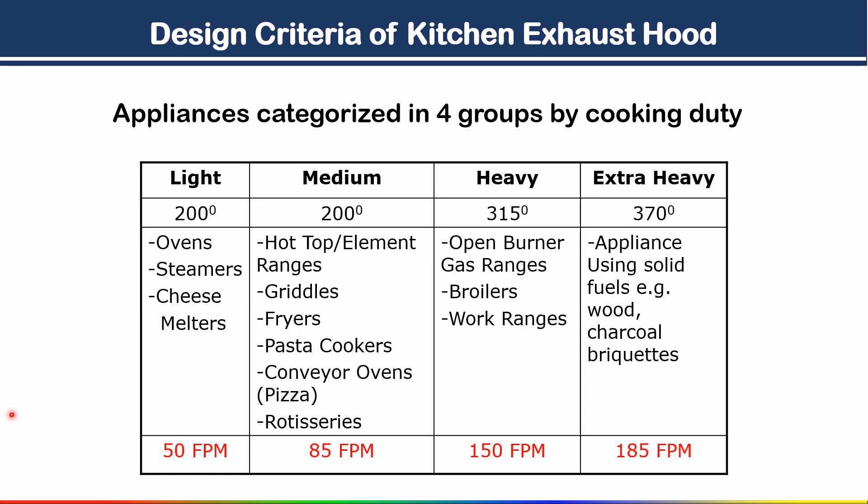Appliances are categorized into 4 groups by cooking duty: light cooking, medium cooking, heavy cooking, and extra heavy cooking. Ovens, cheese melters, and steamers come under light cooking. Fryers and griddles come under medium cooking. A temperature range around 315 degrees corresponds to heavy cooking — generally restaurant cooking is heavy cooking. In residential buildings the kitchen is medium or light cooking only. For commercial buildings, cooking comes under medium cooking. Required face velocity: light cooking 50 fpm, medium 85 fpm, heavy 150 fpm, extra heavy 185 fpm.